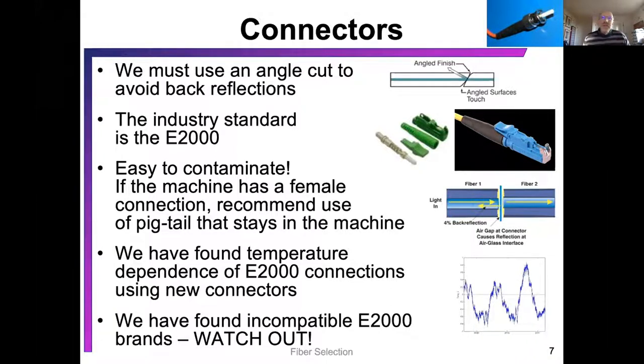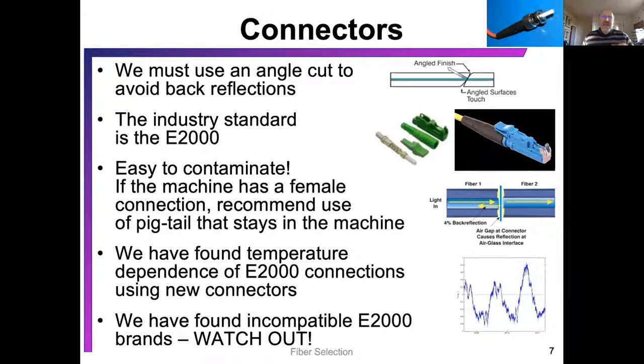The glass we're using is very run-of-the-mill multi-mode glass for the most part, but the way the glass is terminated is unlike what is typically done for telecommunications. We use an angle-polished end on it, not a vertical end. What that means is that back-reflection in the Raman spectrum is bounced out of the fiber, which is really important because that would otherwise contaminate our signals. So when you order your pigtails, use the angle-polished APC finish on the fiber — that's not normal and you have to ask for it.